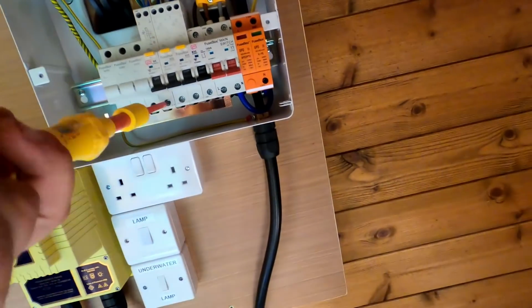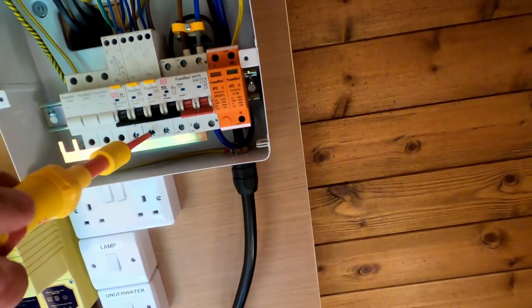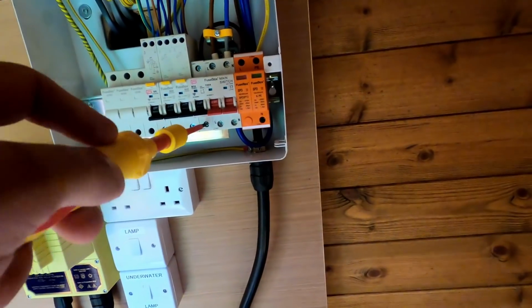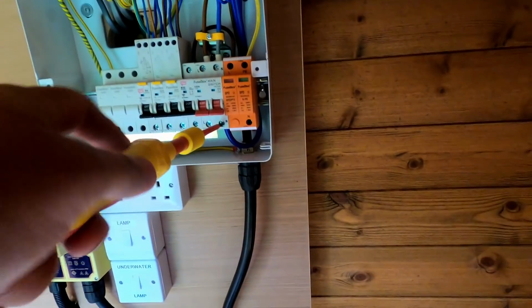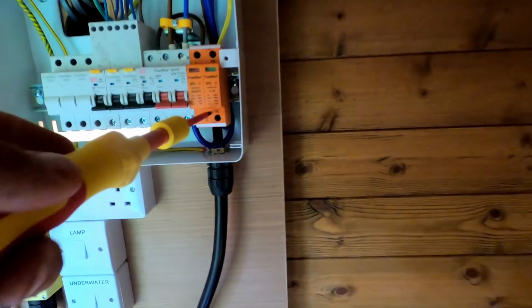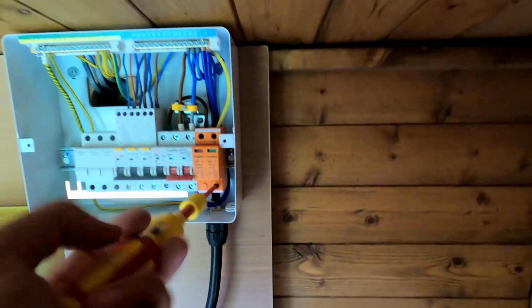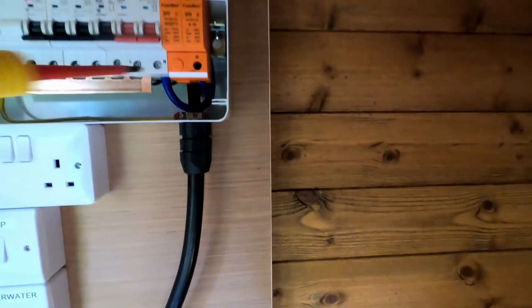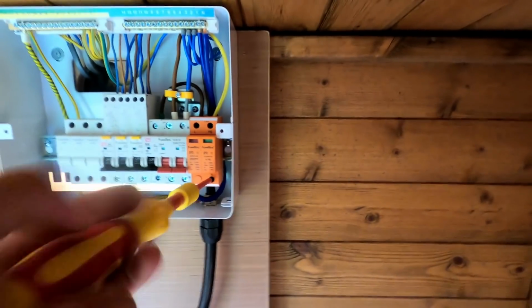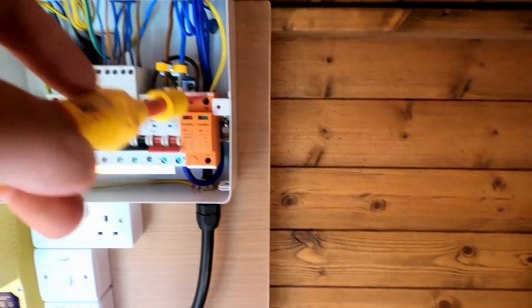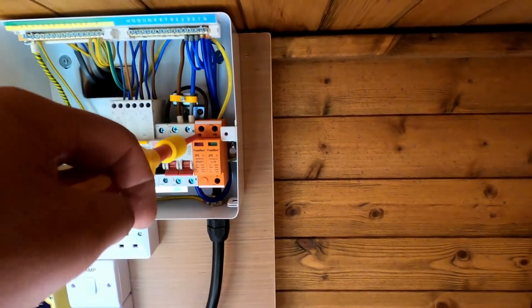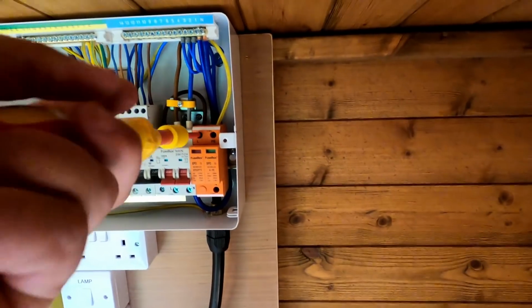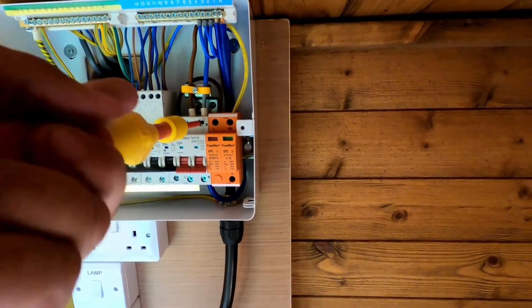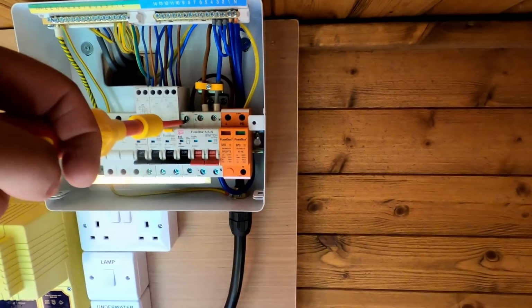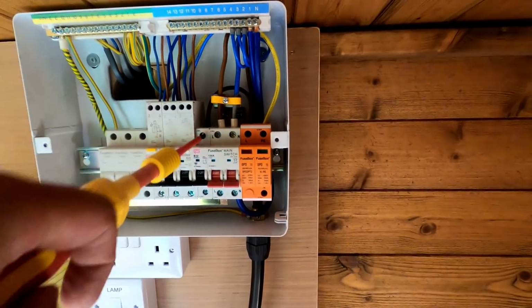2.5. Right, let's have a go. So yeah, I'll do all of them, because that one says 2.5, but it's not even been undone, but it's very loose. So we'll just tighten these up. There we go, last few. Line and neutral, and then the MCB for the SPD, and that's it, all torque tight.